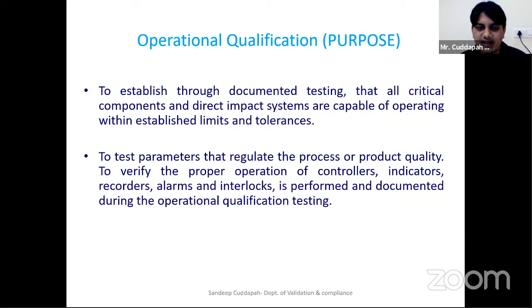Say you have taken a manufacturing vessel. During your process, you are pressurizing that vessel. That vessel will have a safety valve. At this pressure, the safety valve should open. That kind of test you will do in operational qualification, whether it is able to operate or not. You will give certain pressures to induce that valve, and you will see whether it is in operational condition or not. You will verify this in this qualification.